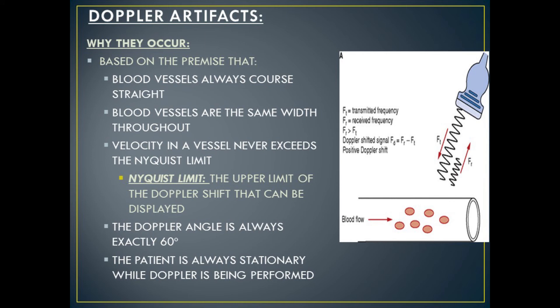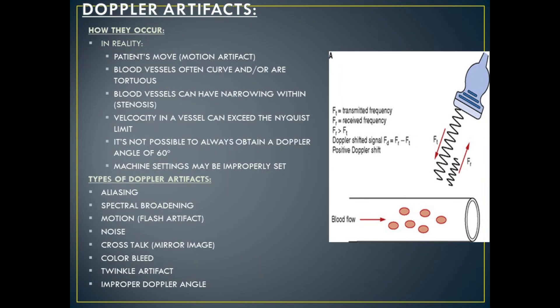Our last category of ultrasound artifacts are Doppler artifacts. These occur when using color, power, or spectral Doppler, based on the premise that blood vessels always course in a straight line, are the same width throughout, and velocity in a vessel never exceeds the Nyquist limit — the upper limit of the Doppler shift that can be displayed. These also occur based on the premise that the Doppler angle is always exactly 60 degrees and the patient is always stationary. In reality, patients move (motion artifact), blood vessels are curvy and tortuous, vessels can have narrowing (stenosis), velocity can exceed the Nyquist limit, a Doppler angle of 60 degrees isn't always obtainable, and machine settings can be improperly set.